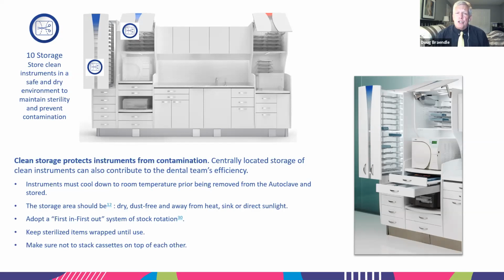And if I have a wet pouch, the membrane on the pouch is permeable, and I lay that down on a countertop of a sterilization center operating with an ultrasonic with the lid off, we've screwed the pooch right then and there. We've done everything perfectly, but then I've taken a wet, porous membrane on a bag and laid it on a contaminated surface, and we have a really good potential of undoing all the good work that we have already done. So please, please, please make sure in all of your own offices, there is never a case where an ultrasonic should be running with the lid off, unless you're doing a foil test. Other than that, I'll give you that. But with instruments, always have the lid on.